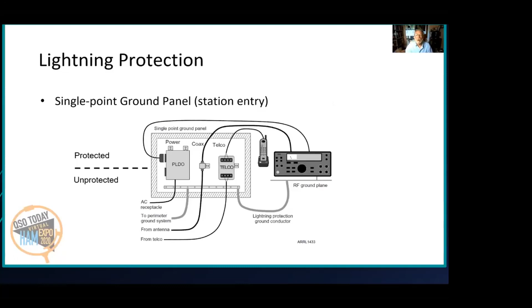Don't give lightning a path around your protectors. Lightning's happy to jump between the unprotected and the protected stuff if you bundle it all together. So even if it looks a little clunky, make sure you keep your protected cables away from the unprotected ones. Here's some examples of what goes on your single point ground panel.